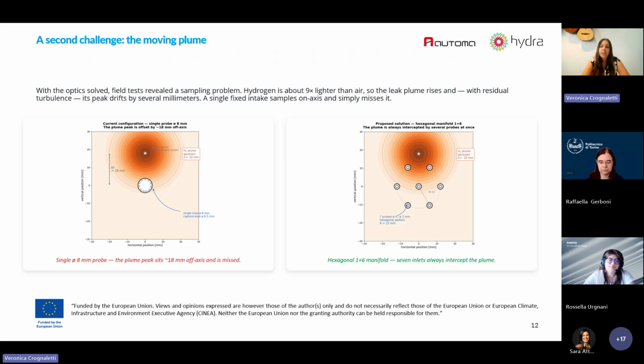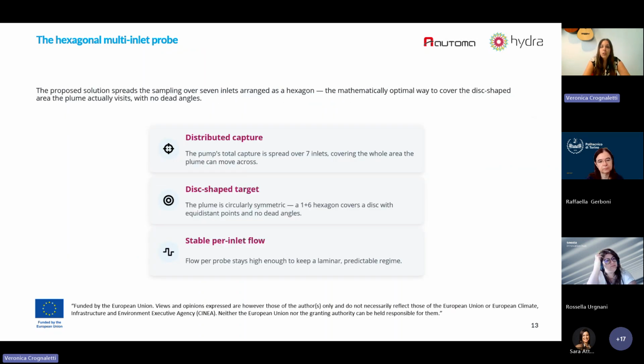The current configuration of the probe is a single probe of 8 millimeters, but we are now designing a new solution, a hexagonal probe with 7 inlets. This proposed solution is able to spread the sample over these 7 inlets, so we have no dead angles. We have a distributed capture and a stable per-inlet flow.